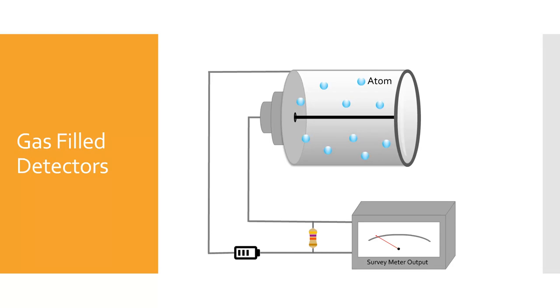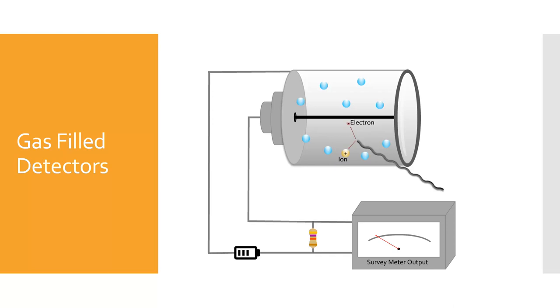We will start with gas-filled detectors. There are four main types and all four use the same basic principle to detect and measure radiation. We will review the process and then discuss the different types. The basic premise starts with ionizing radiation passing through a container, often a cylinder filled with air or gas. The radiation interacts with a gas atom by ionizing it. Ionization is the process of removing tightly bound electrons from an atom, so the more ionizing radiation, the more ionizations will occur.